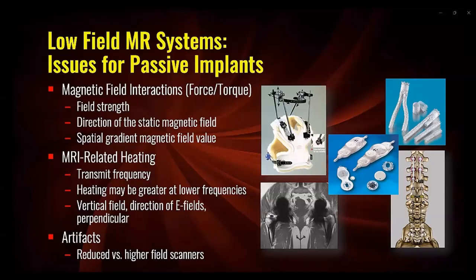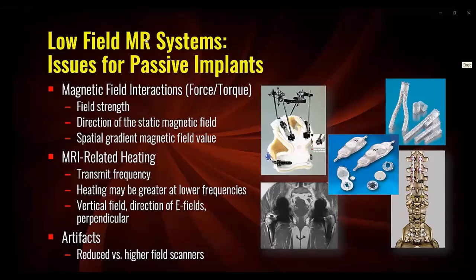Notably, heating has been reported to be greater at a lower frequency than at a higher frequency, depending on the length of certain implants. For vertical field scanners, further consideration should be given to the direction of the E-fields, which is perpendicular.